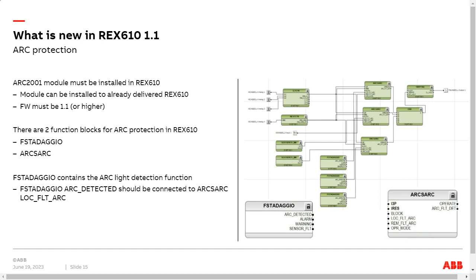Then looking at the arc protection function, if you're familiar with, for example, 640, you can see that we have one additional input, this local fault arc. The idea is that you take the arc detected from the arc function and connect it to this local fault arc, as you can see in the big picture on top. The other change is that on 640 you have an output called alarm, which supervises the sensor. Now we have moved it to the ARC function block instead, and it's called sensor fault, not alarm. So this is how it works in 610.